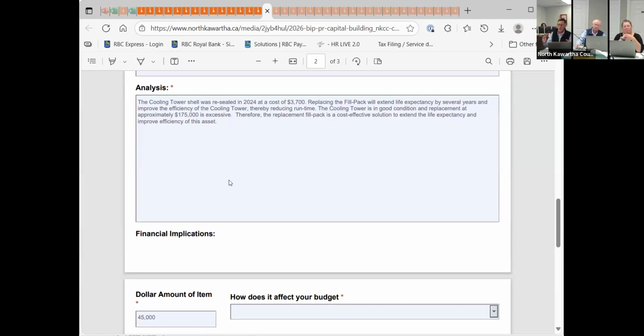We've noticed the cooling tower isn't performing as well this year, especially in warmer weather when high pressure limits get right to the top. This is because the fill pack is reaching the end of its life expectancy. A new fill pack would keep head pressures down and reduce electricity use.